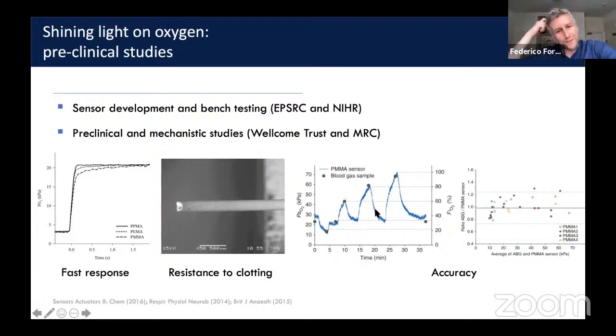And then obviously we repeated what was done on the bench. We looked at the accuracy of these measurements. The graph here towards the middle shows a period of 35 minutes on the horizontal axis. And on the vertical axis on the right is the fraction of inspired oxygen. So the animal at this point would have been given 100% oxygen, or at the beginning of the experiment would be given room air oxygen, which is about 21%. And on the vertical axis, we see the partial pressure of oxygen, where we have two signals here. We have some green dots, which are a standard blood gas sample. So it's taken with a syringe, as is normally done in patients. And then together with that signal, we have in blue the continuously recorded signal, which was recorded with our sensor.